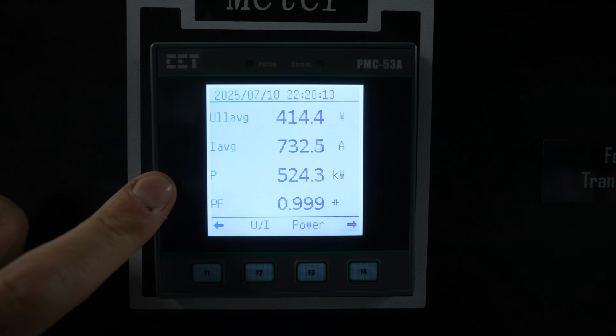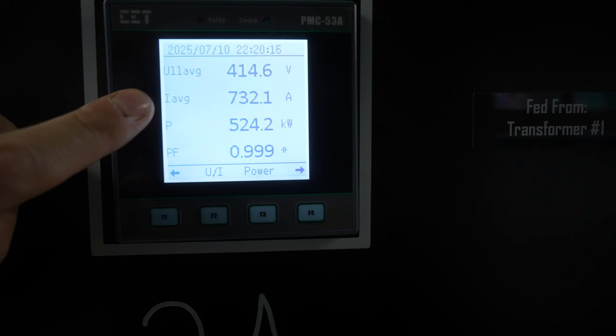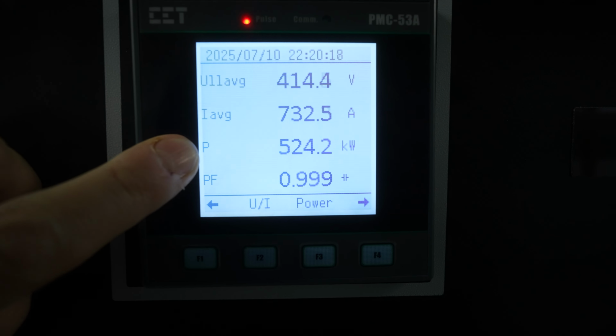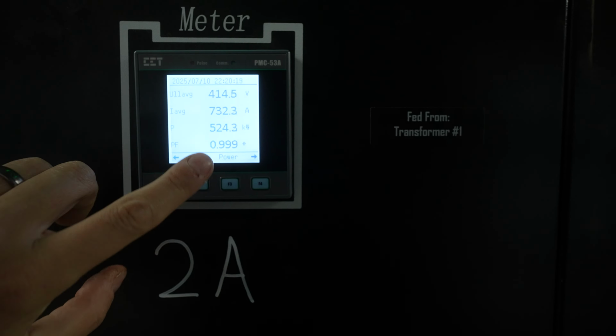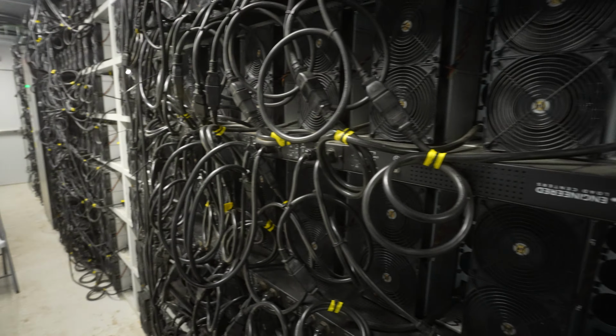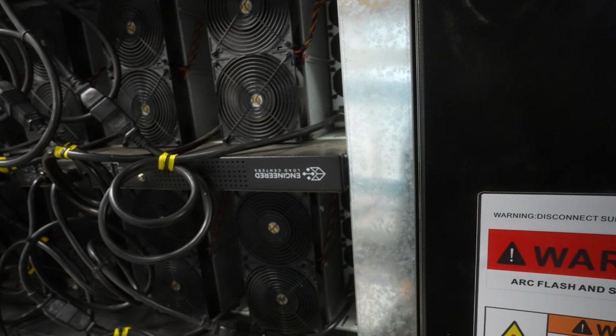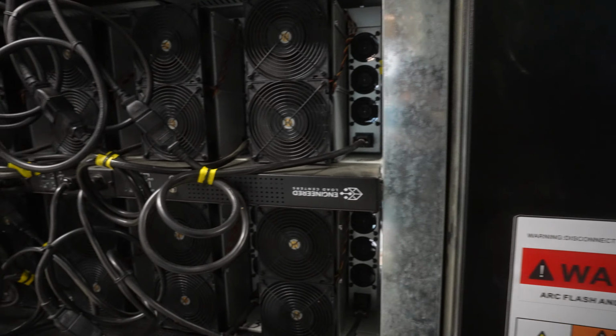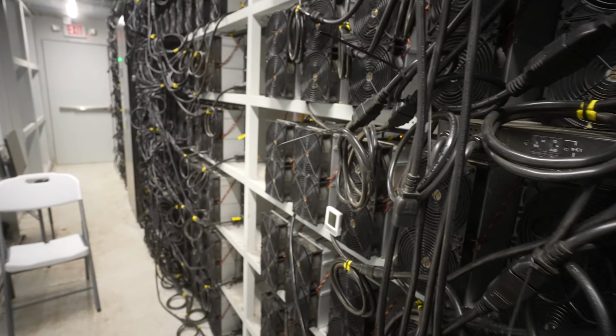Each cabinet has a meter. You can see here the voltages, the amps, and the KW load. You see it's 524, so that's a little bit over - 24,000 watts over. Each cabinet is 500, so he's a little bit over on this cabinet, but they do get that 1 megawatt, which is fine.